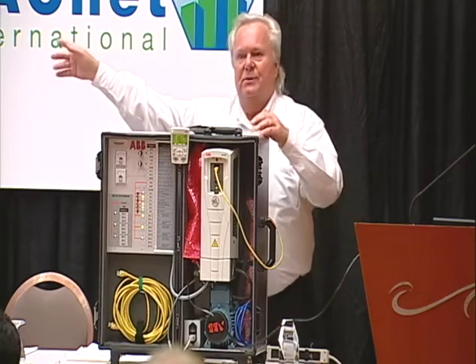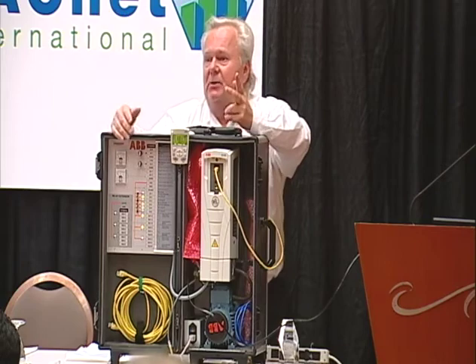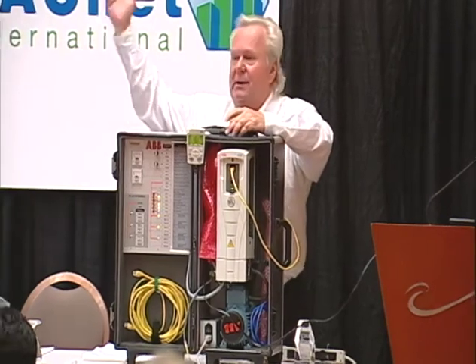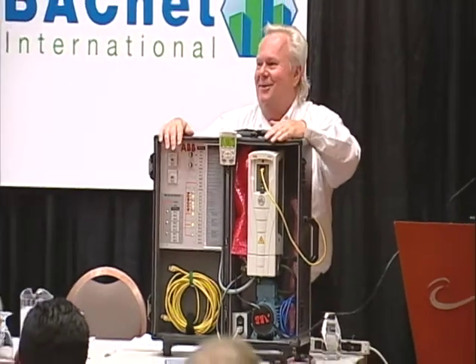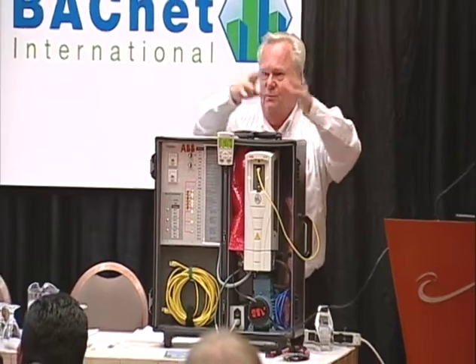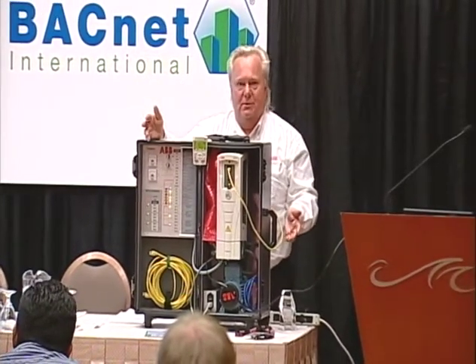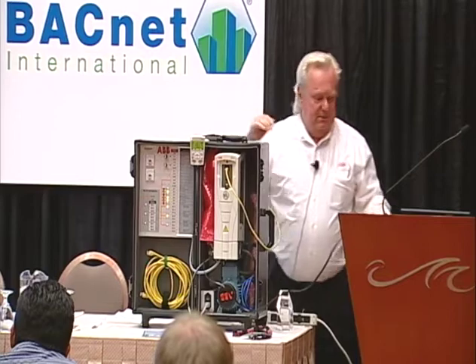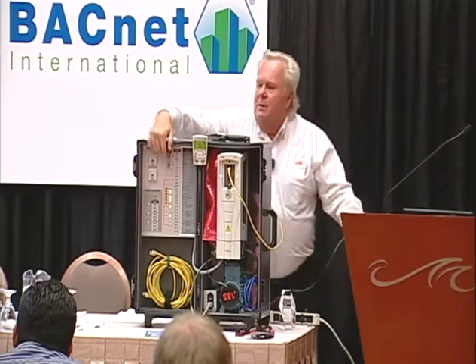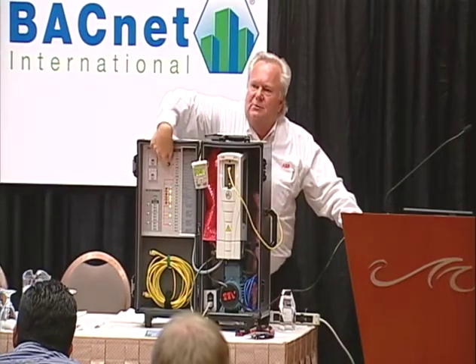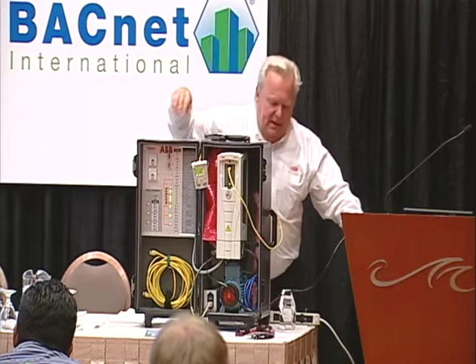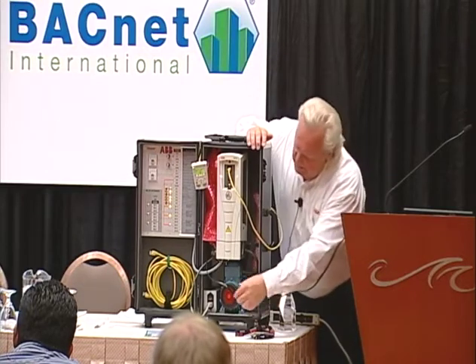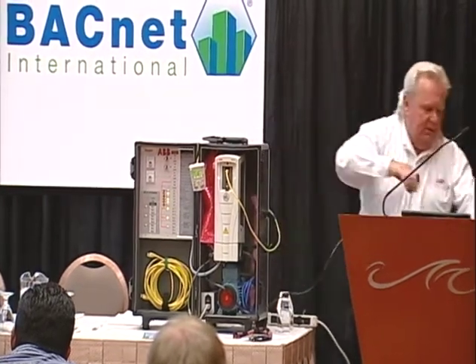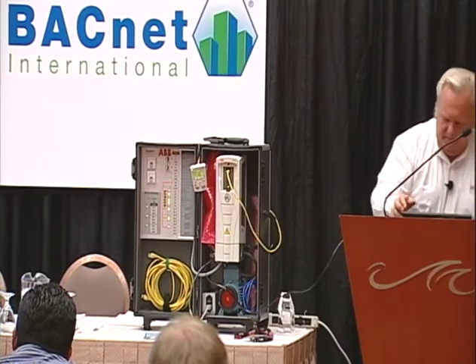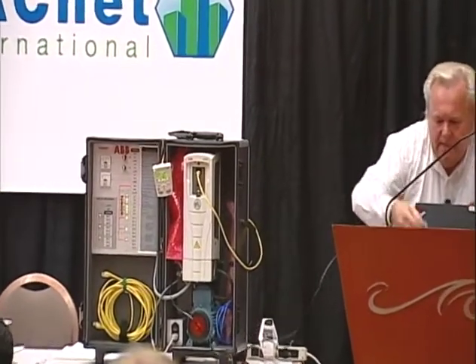So by doing it this way, I send 2 commands a day across the BACnet wire. Occupied and night setback. Other than that, I've taken the bandwidth and opened it all up for the other stuff going on the wire. That's number one reason. Number two reason, I'll show you, is because if I have the drive doing the math, I can cause a loss of communications. So somebody cut the wire, right?